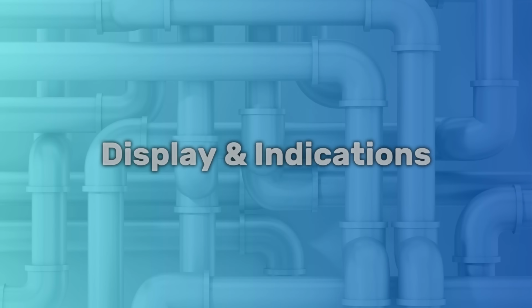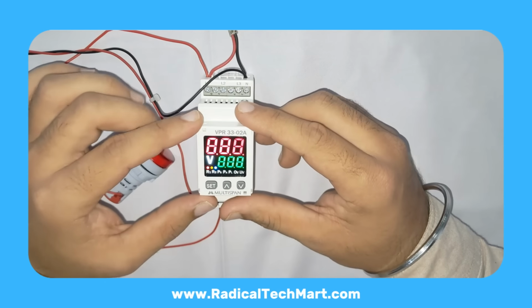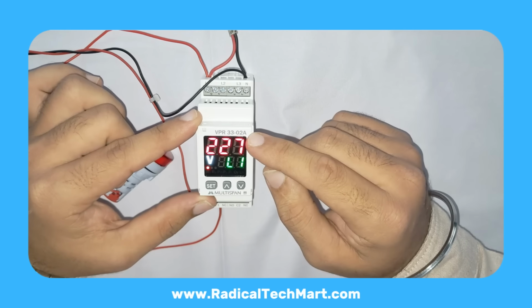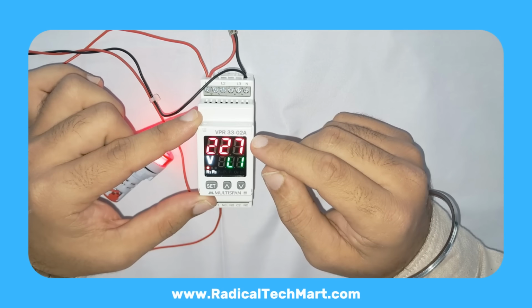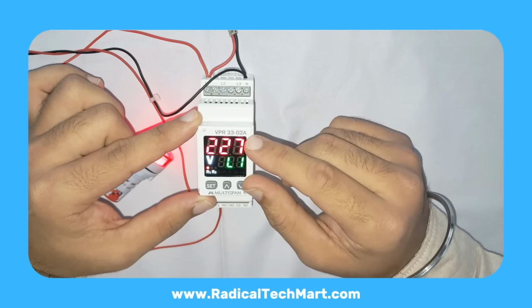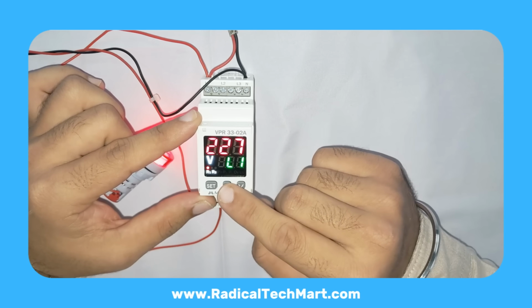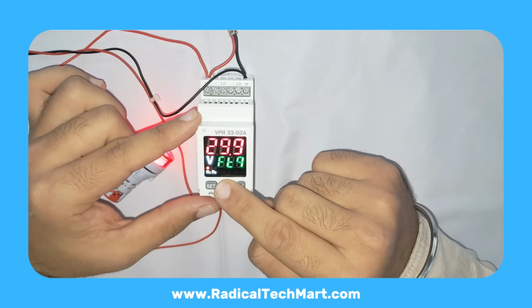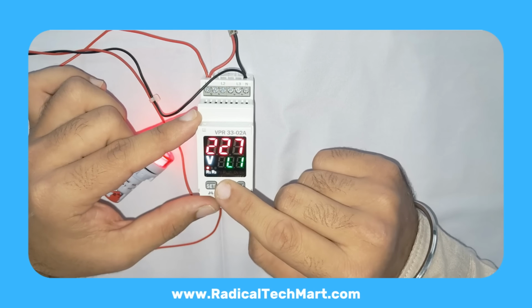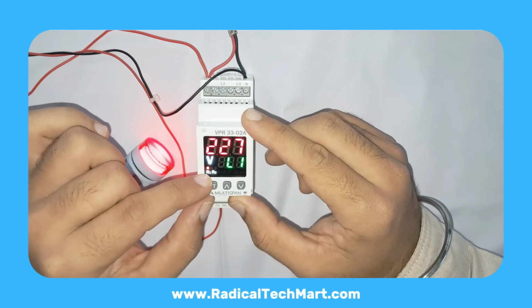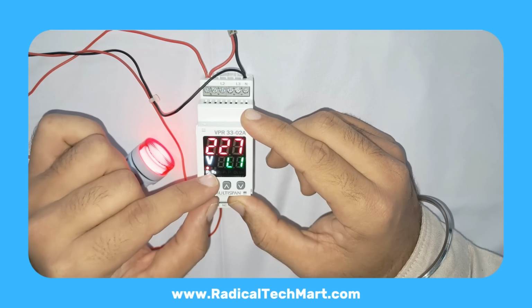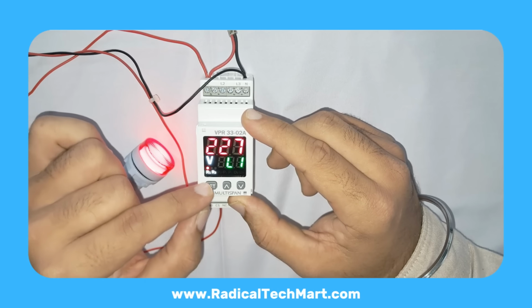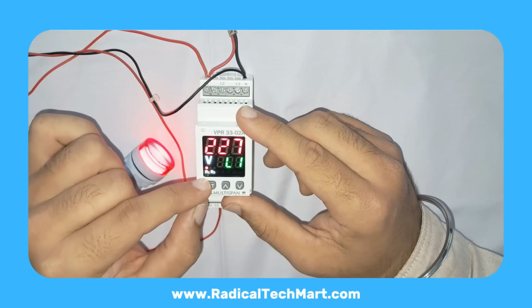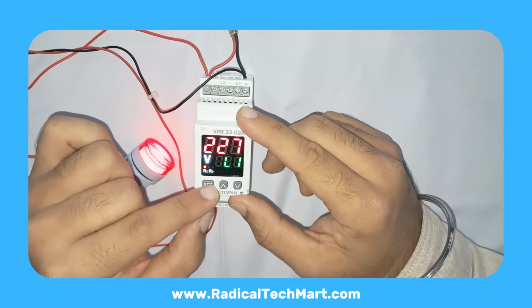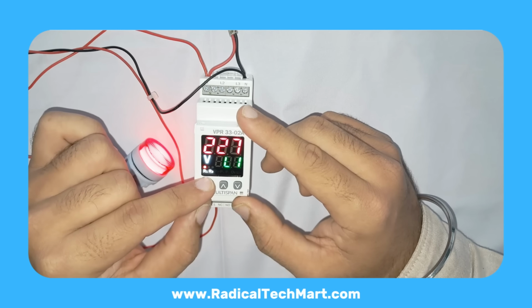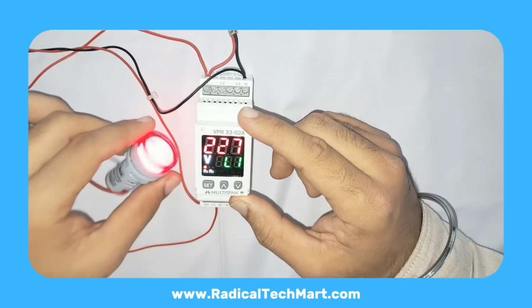Display and indications. Now as soon as we power up the relay, on the display you can see the phase voltage. We have currently configured it in single-phase mode because we are using only one phase here. If you use it in 3-phase mode, by pressing the UP button, you can scroll and see all 3-phase voltages. At the bottom of the display, you'll see 3 small dots. These represent the R, Y, and B phases. You'll also see indicators for R1 and R2. If the symbol is on, it means that the relay is energized. If it is off, it means that the relay output is off. Right now you can see that our relay output is on.